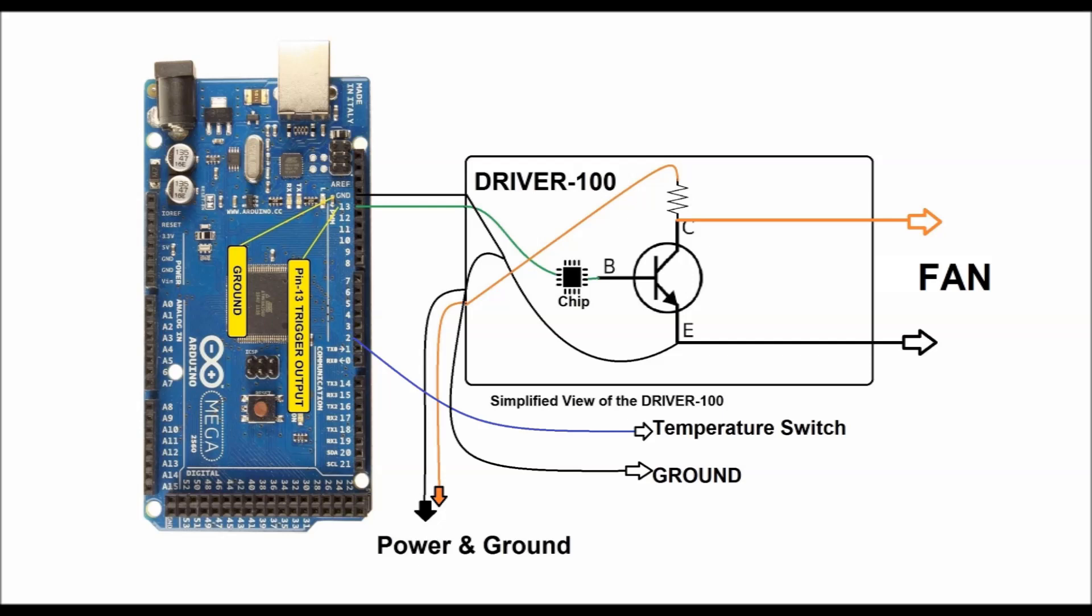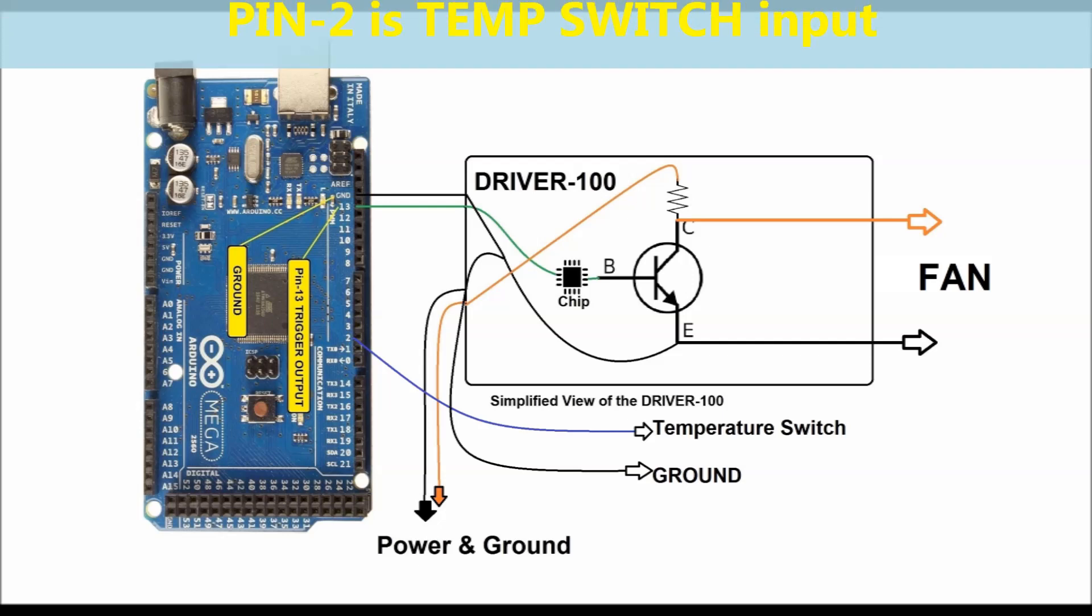A quick glance at the wiring diagram, we can see the driver 100 board attached to pin number 13 and ground. The green lead is the one that actually controls the output transistor. The driver 100 board, that module is connected to the fan, and that's the one that's going to control the motor directly.